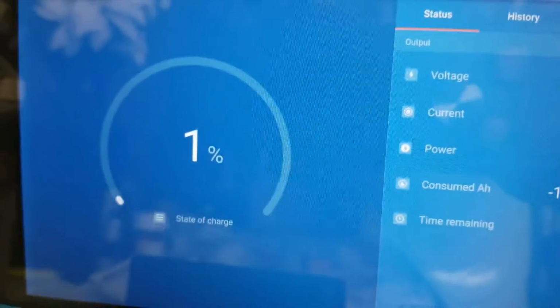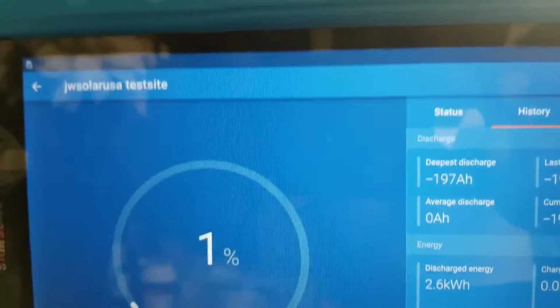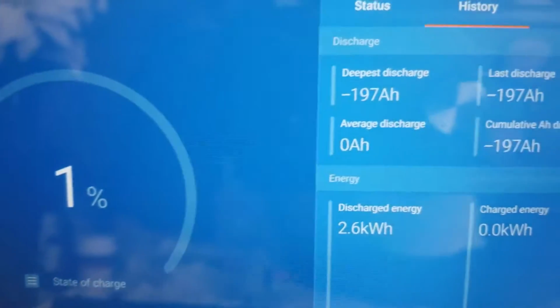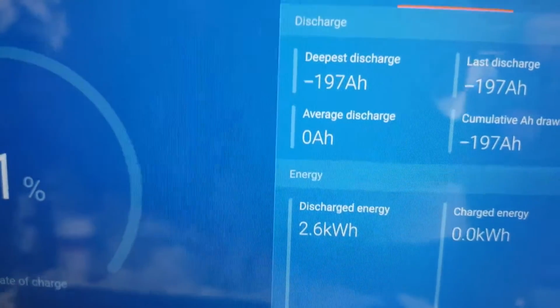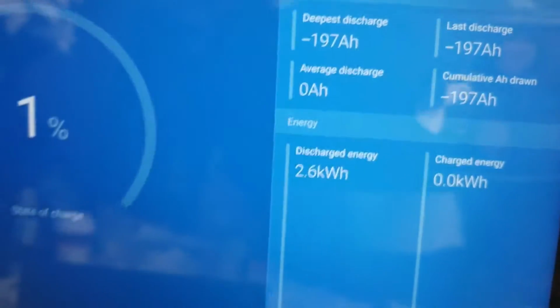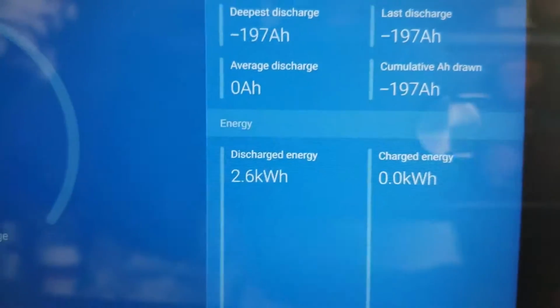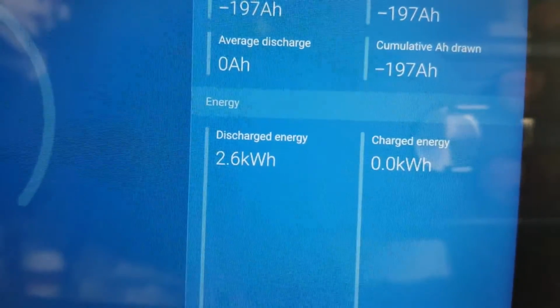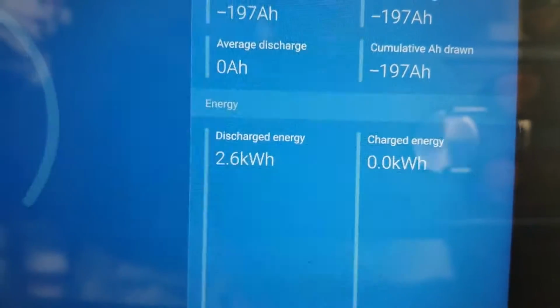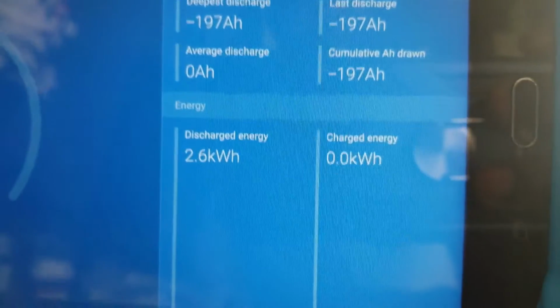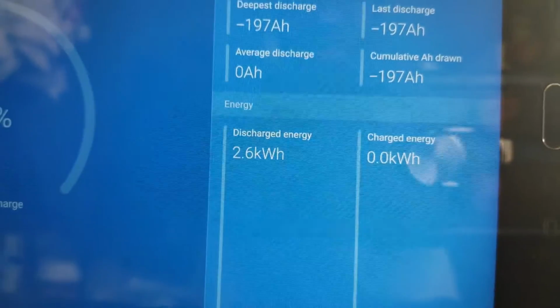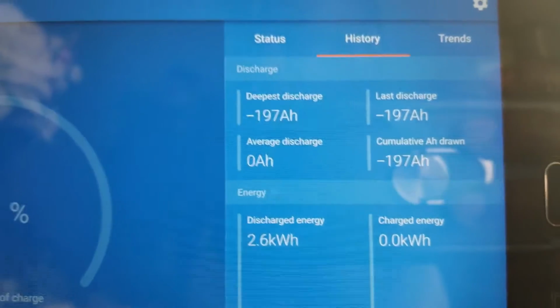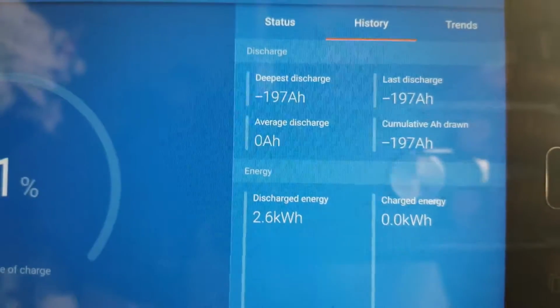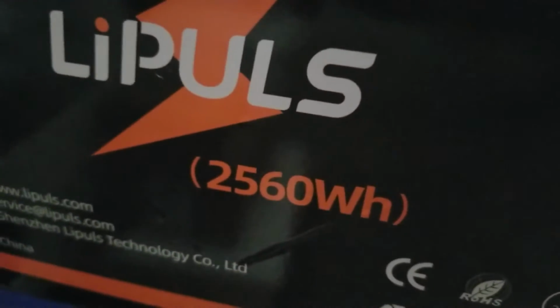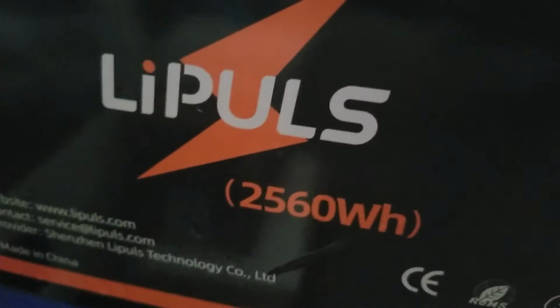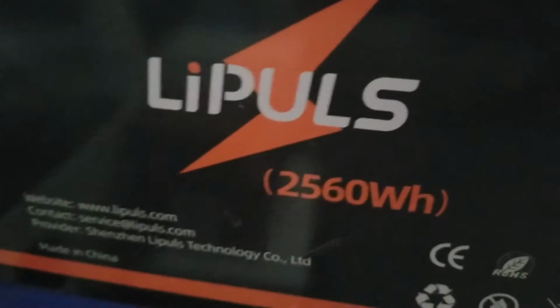Let's check the history here. If you check the history, it says the deepest discharge was 197, and you see the discharge energy is 2.6 kilowatt-hours. That means we already put out about 2,600 watts, close to the 2,560 rating. So on the wattage, we already passed the test.